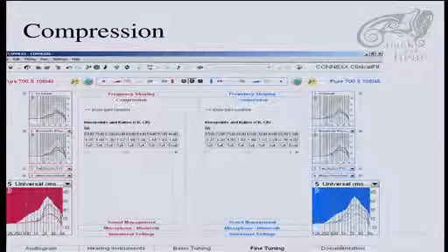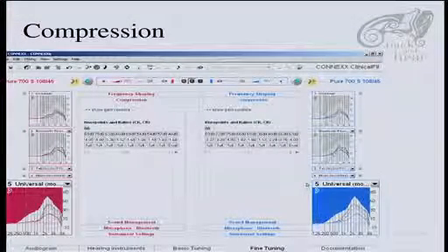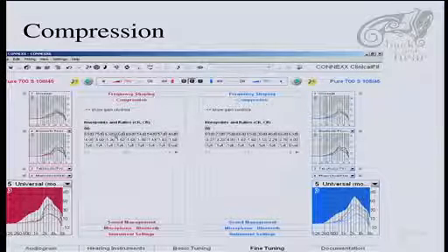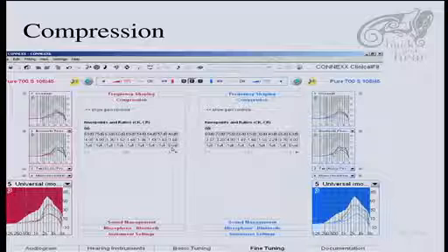In the hearing adjusting software, it looks like that. This is actually an example only from Siemens. Every brand has their own adjusting software, or tuning software, so this is just an example. So here you have the knee point in the first row and the factor by which it is compressed. And the third row is a factor regarding how fast it should react. So sil means syllable, so within one syllable it's adjusted to the right volume.